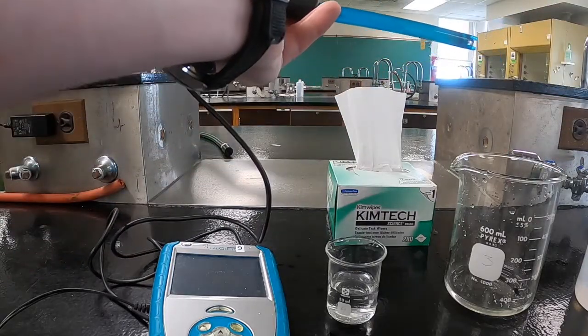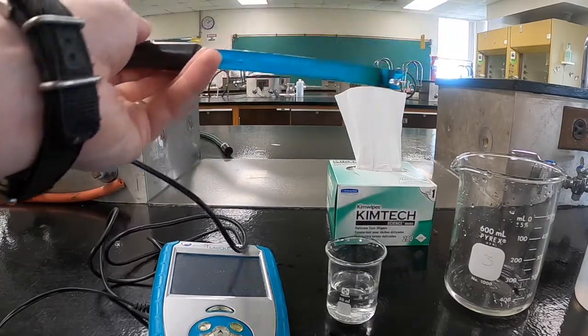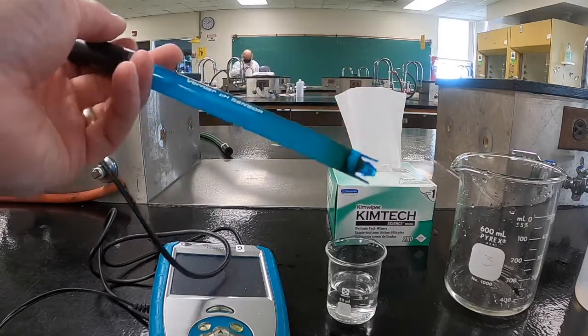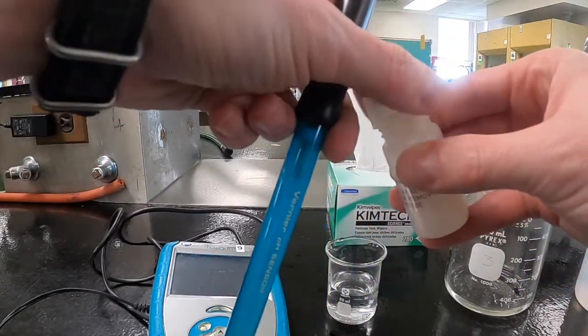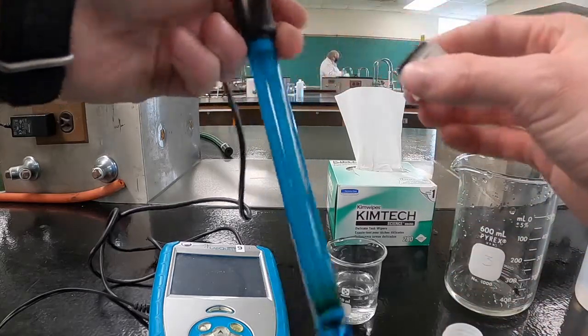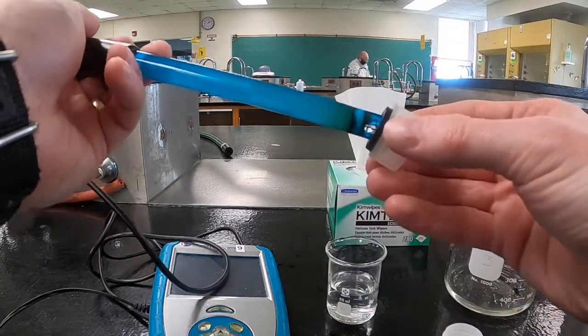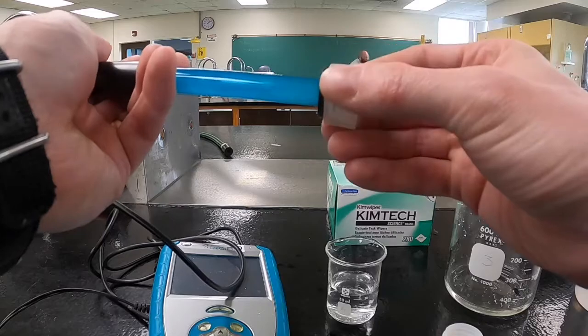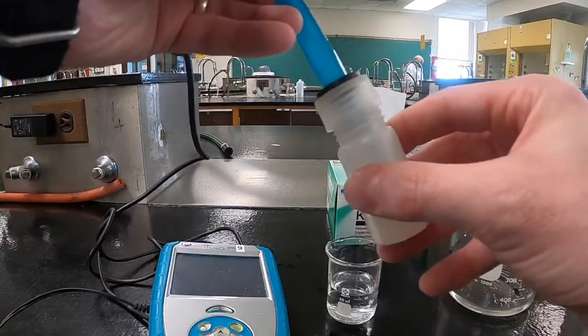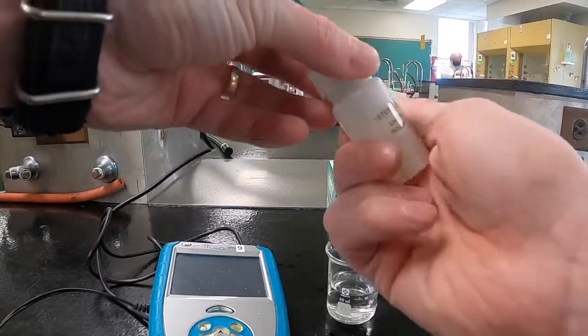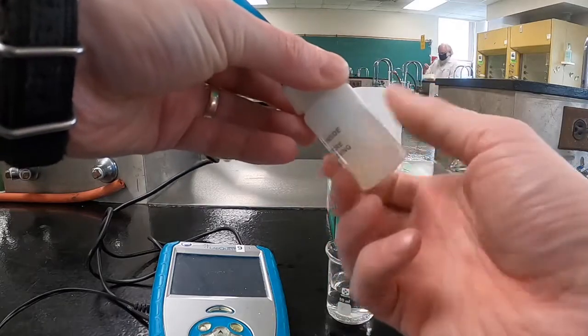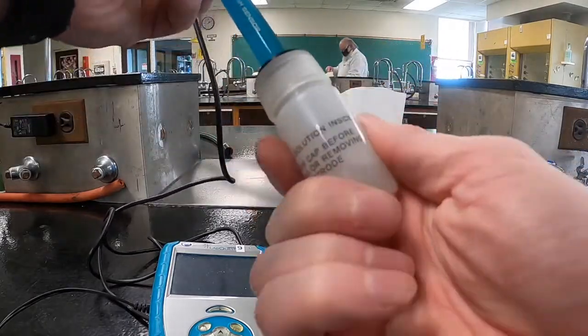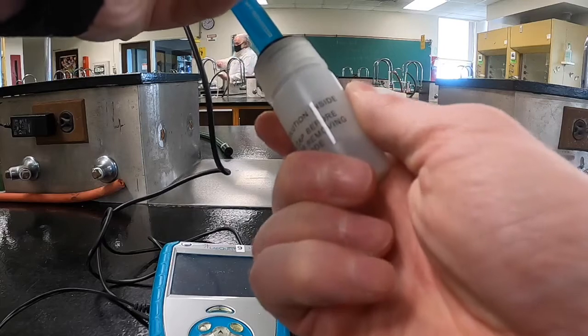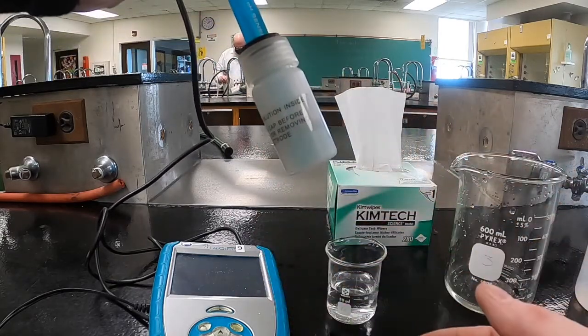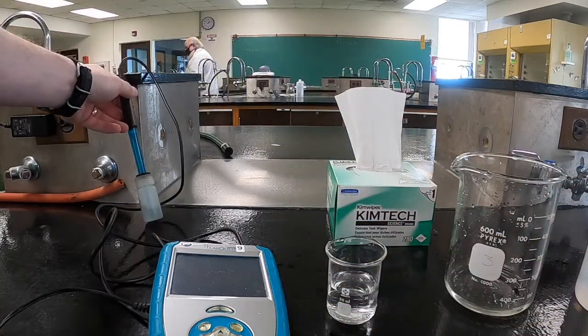At this point, you can do one of a couple of things. You can either continue on to test your next sample, or you can put the probe away. To put the probe away, you simply place the cap back onto the probe, and then screw the cap onto the storage container, and adjust the probe down so that it's fully immersed in the storage solution. Once you've stored the probe, you can simply turn the meter off and unplug the probe.